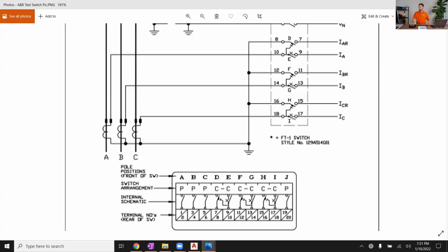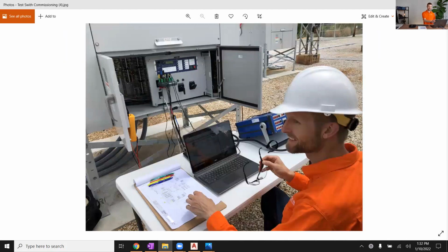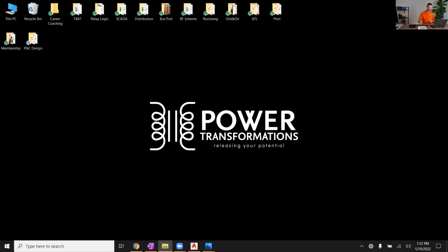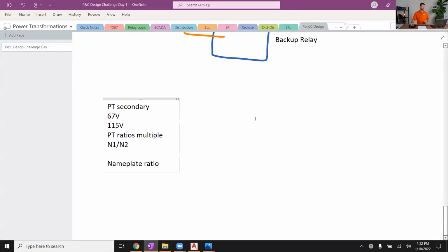What's the purpose of a single ground in the CT secondary circuit? Good question there. If you have multiple grounds, what actually could happen is you could have fault circulating ground currents through your substation ground grid. And so that's why you want one and only one ground point on each CT secondary circuit. Looks like Sean jumped in there. Great job. So I think this is the last question I'm going to handle for today. If you have follow-up questions, we can address those at the start of tomorrow.